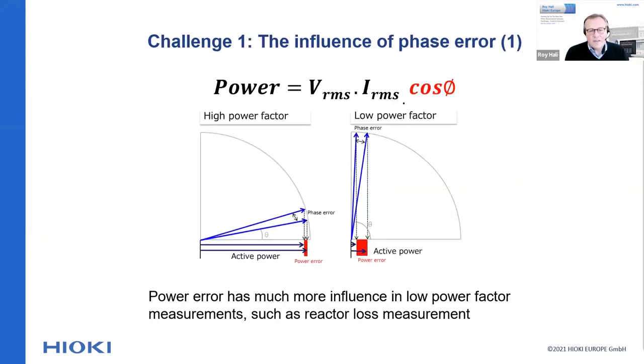The first challenge that we face is the influence of phase error. I like to explain this with the two phase diagrams on this slide. On the left side, you see the vector diagram of a device with a high power factor, for instance, a power resistor. In this case, the influence of the power error, the red area, is very small in comparison with the measured active power. However, when we look at the right-hand side, we see that the power error is very big in comparison with the measured active power. Therefore, as soon as you measure at low power factors, it's extremely important to compensate for the phase error. So how can we achieve that?